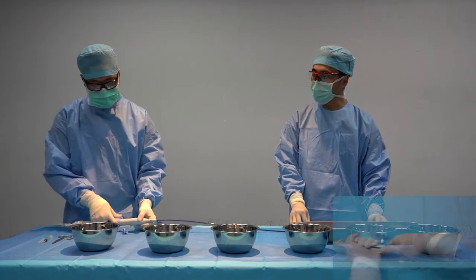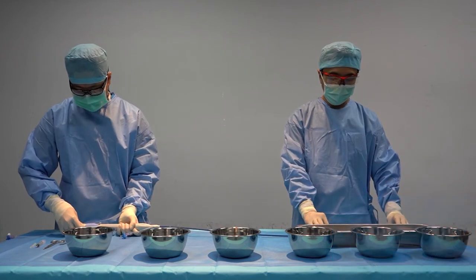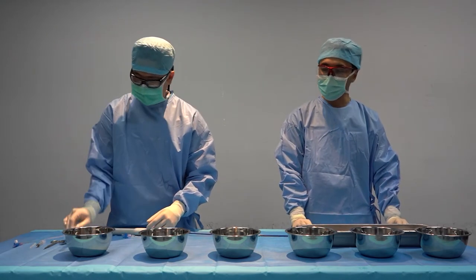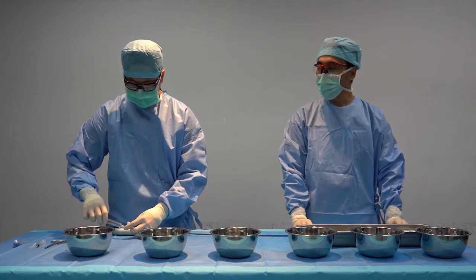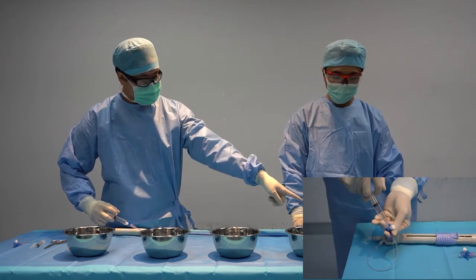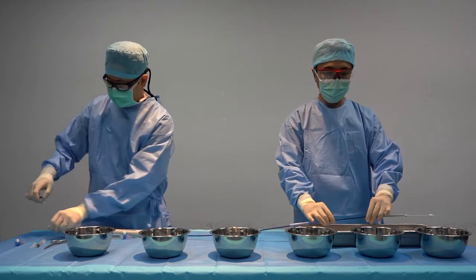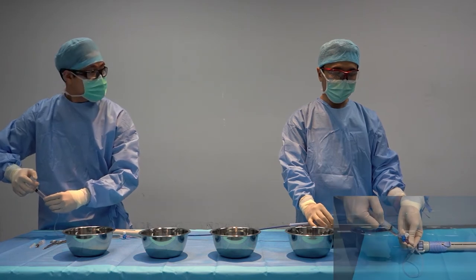Hold the handle with your left hand and push the thumb pad with the right thumb and slide the blue handle back. Rotate the micro knob clockwise until a click sound is heard. All flushing is done using normal saline with heparin. Flush the outer casing canal and conveying canal of delivery system. A quick tip is to gently press or roll the outer tube of delivery system with your finger when it feels difficult to flush. Please ensure the other purge tube is adequately flushed.